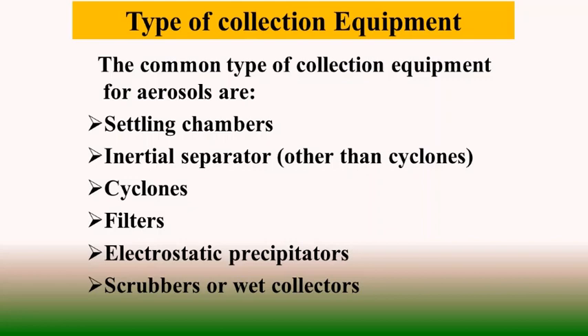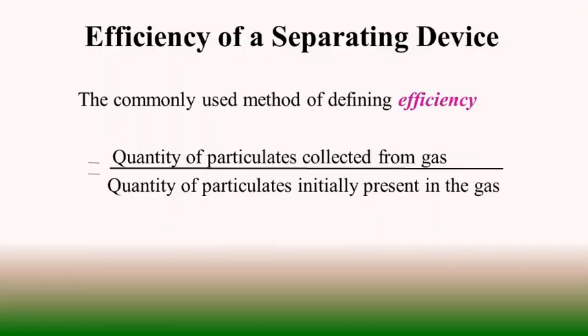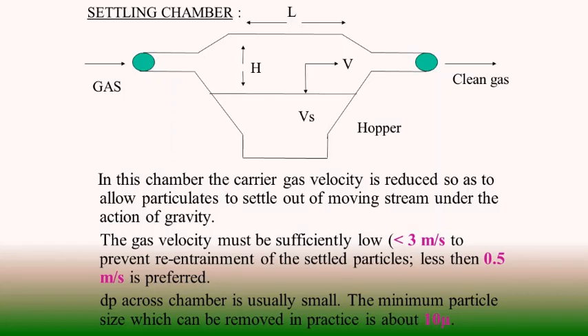The common types of collection equipment used for separating dust from the exhaust gas are basically settling chambers, inertial separators other than cyclones, cyclones, filters, electrostatic precipitators, and scrubbers or wet collectors. The efficiency of the dust control equipment is measured by the quantity of particulate matter collected from the dust-laden gas flowing through the equipment, with respect to the quantity of particulates initially present in the gas entering the control device.